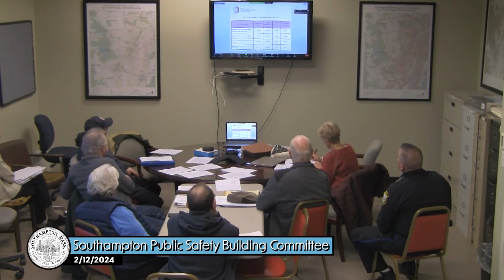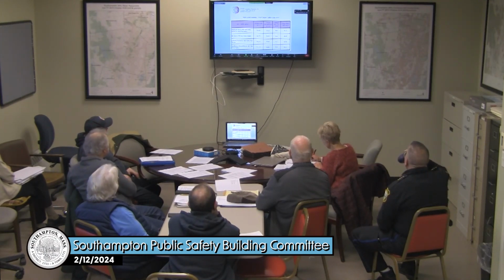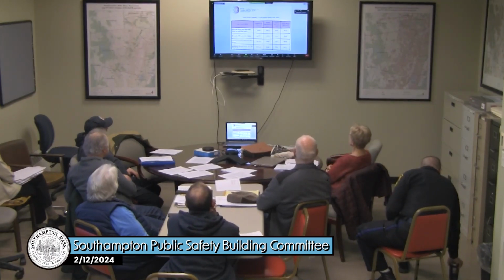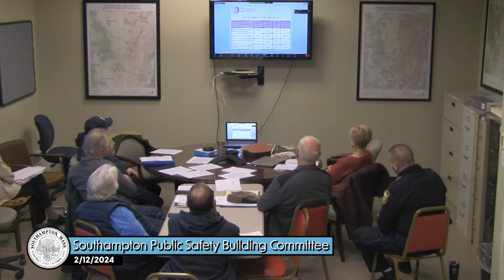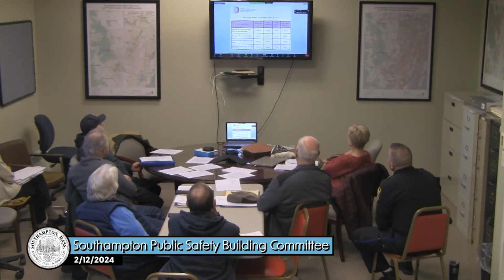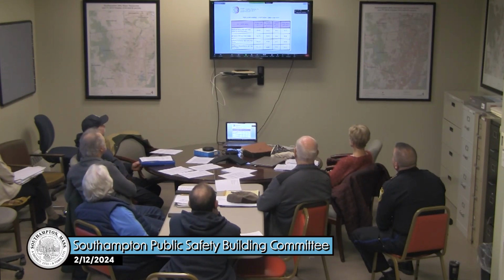Is there another option, Bobby, the geothermal central plant, not VRF? You could do geothermal instead. You could pair the hydronic option with an air source heat pump chiller, or you could do instead a groundwater source chiller, and it would operate the same way, except you're rejecting your heat to the geothermal well field instead of to the air.